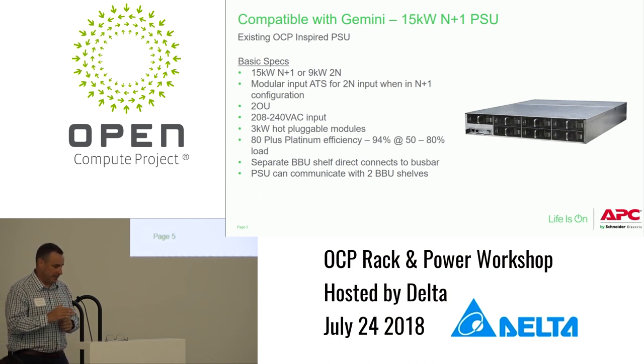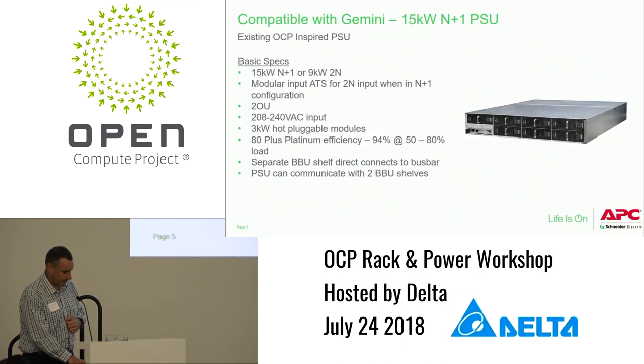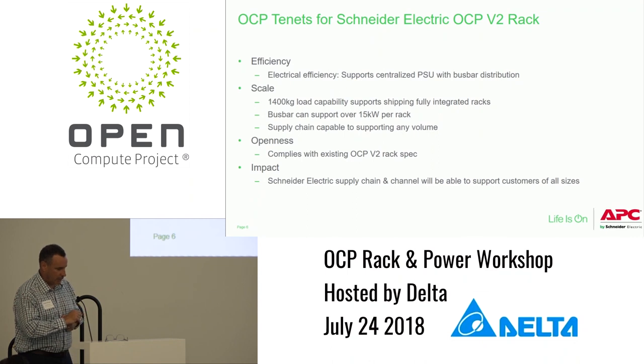The BBU shelf directly connects to the bus bar. From a communications perspective, you can connect up to two shelves if you want longer run time than the nominal 120 seconds. You can see in the drawings there are two slots and two places to connect the power shelf and the BBU. From an OCP tenets perspective, electrical efficiency is 94% and it supports centralized PSU with bus bar distribution, which provides significant savings in the number of power supplies compared to traditional IT.